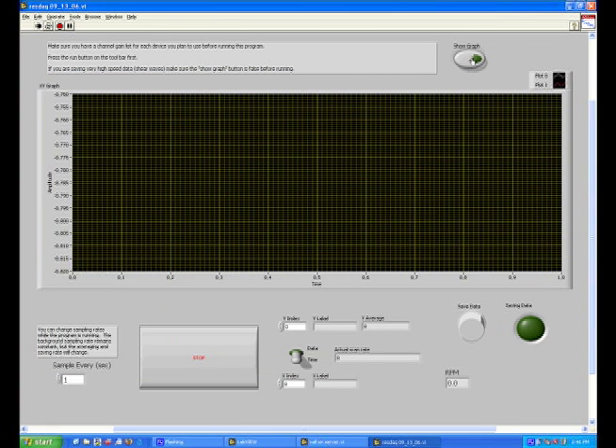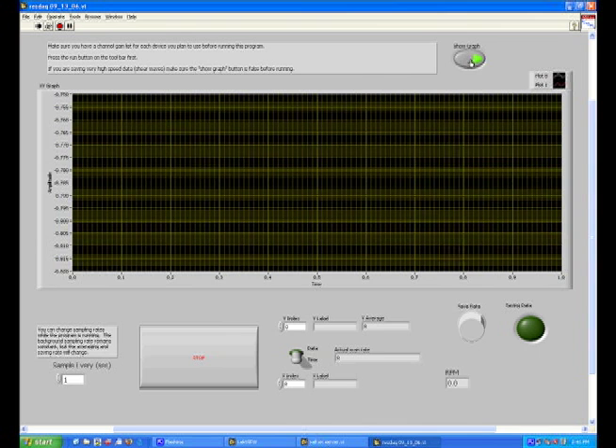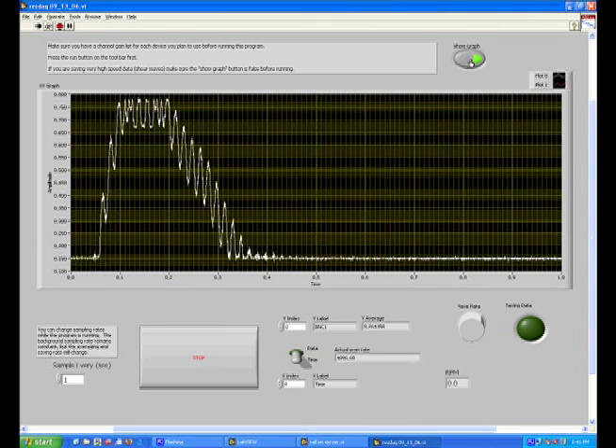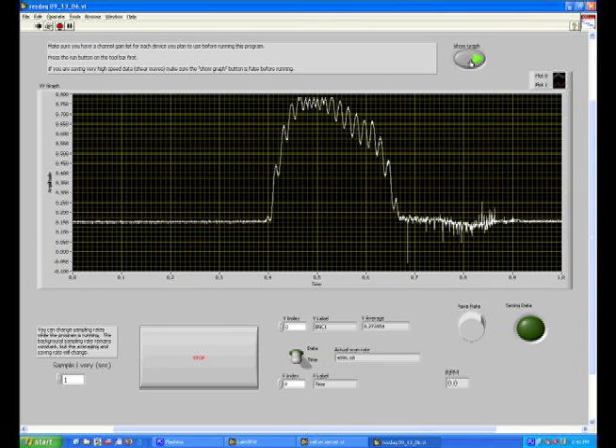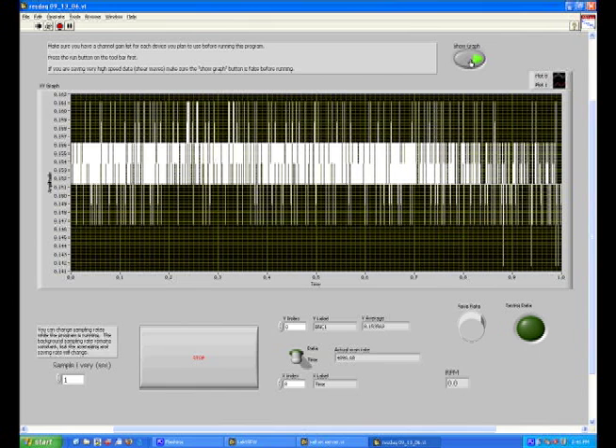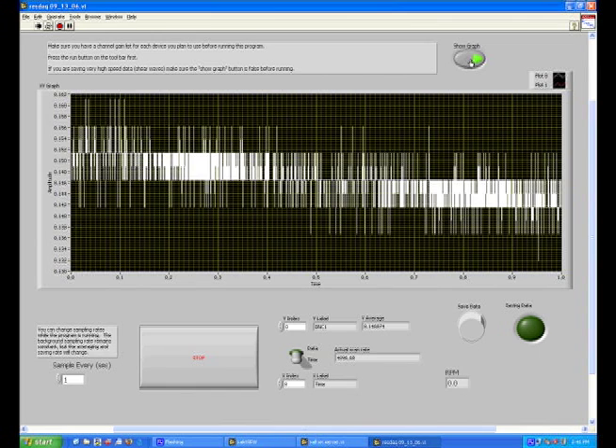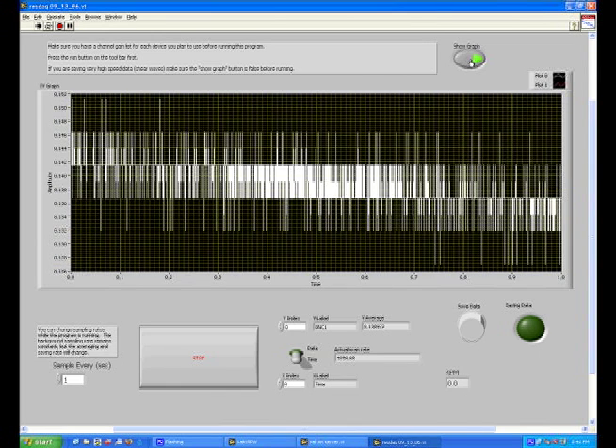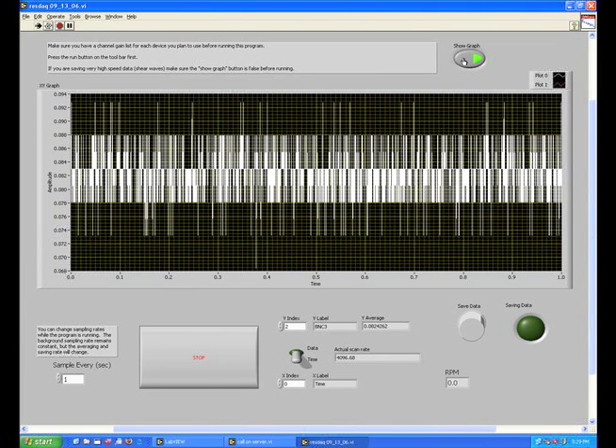If a graph is not being displayed, click show graph on the upper right hand side of the screen. The arrow should turn green and show a running graph. You should first verify that there is no more than 30mV of noise between high and low peaks.